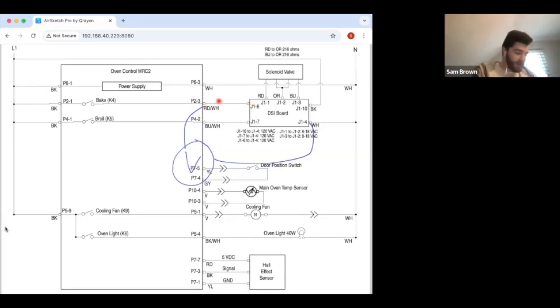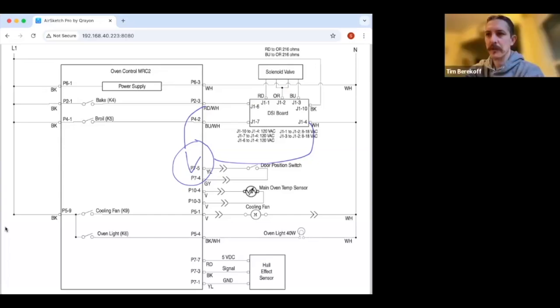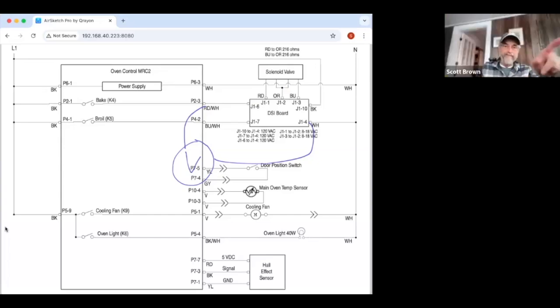Because that's the DSI board signal that it's supposed to be running the valve. Once it loses that signal, it will stop running the valve, close that solenoid, and put out the high voltage in the not-shown electrode wire. I think they don't show the electrode wire here because they don't want techs going in with their meter trying to measure that voltage.